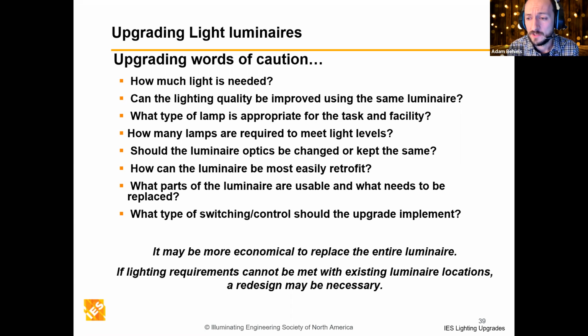What types of switching control should the upgrade implement? Keep in mind the limitations - type A lamps still go through a ballast, so you're still up against the same dimming challenges fluorescents had, probably with an extra challenge running the LED. So dimming is mostly off the table with type A ballast-compatible lamps. But keep that in mind when looking at retrofits. Maybe they want more control, so oftentimes they might just want more switching zones, which takes some rewiring, but that can often be better than a lot of the automatic control solutions if they just want a little more control in their space.